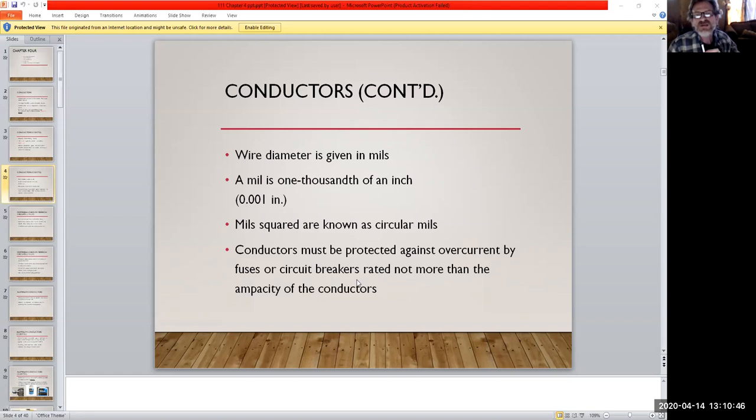And these things take a little time to trip. I mean, fuses, it's not like instantaneous, right? Same with circuit breakers. There are literally seconds involved. And some fuses you can get are quicker. And they've got ones that are even called slow blow, which means that they literally take time. And there's a reason why, because whenever you charge something up initially, let's say you start a motor, when it first starts up, they have something they call the instantaneous rate of charge.